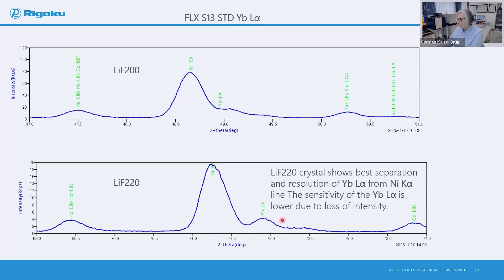Here's some more examples of germanium. The LIF220 crystal shows best separation and resolution of germanium K-alpha. And the sensitivity of germanium is now lower due to the loss of intensity. Once again, you can see the intensity scale here. Good separation, so at least we can now define a proper peak angle and a proper background, but it offers you best separation, but low sensitivity.